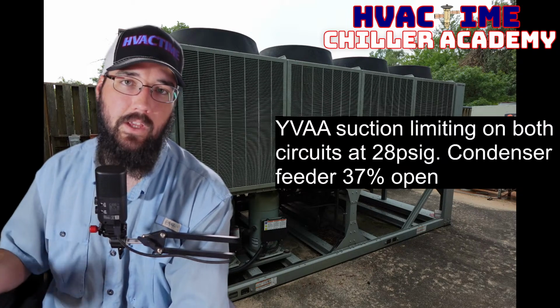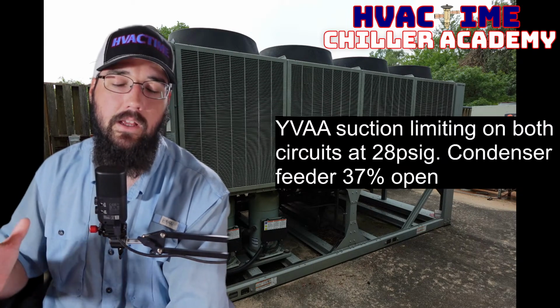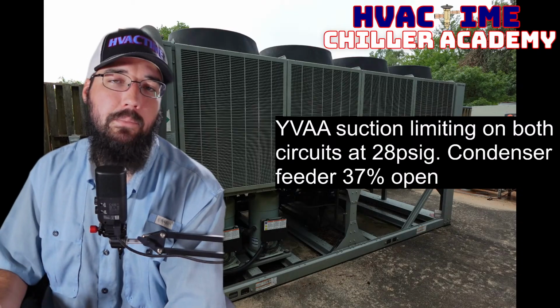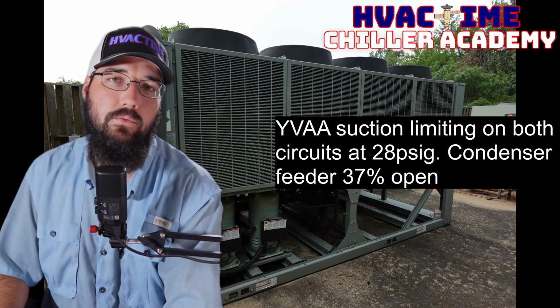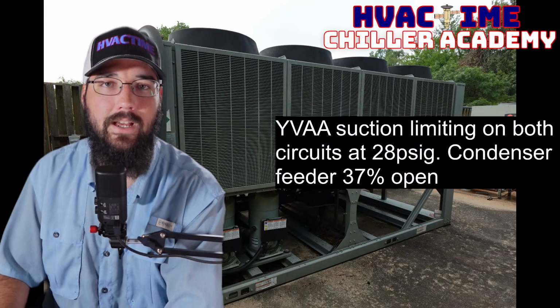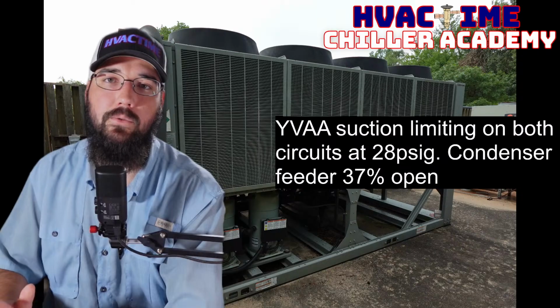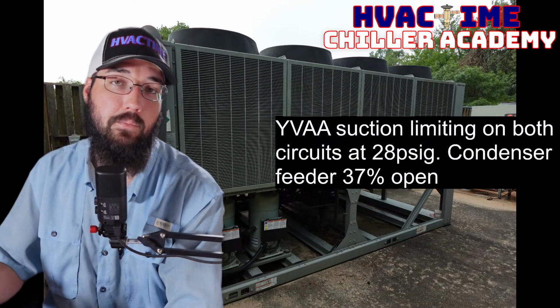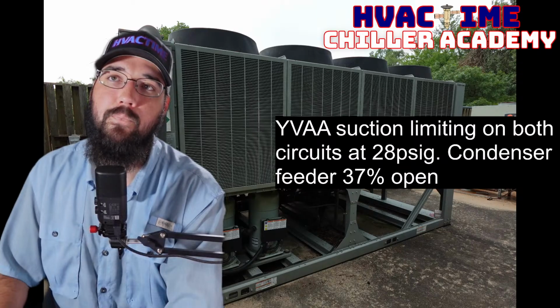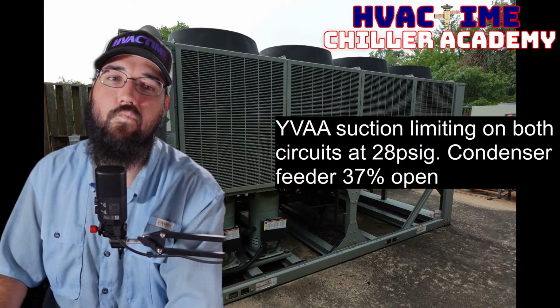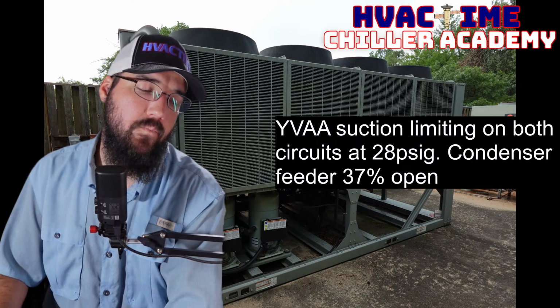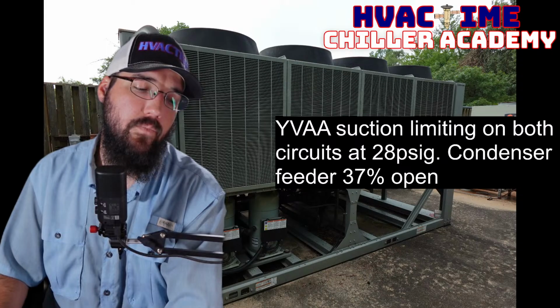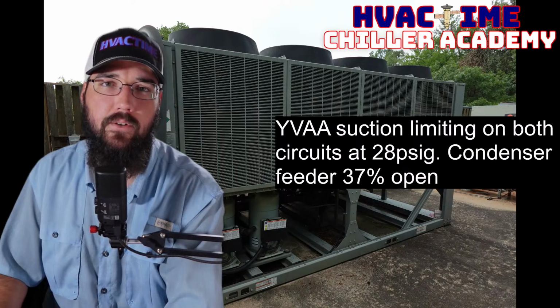Now you might say, okay, well, flow hasn't changed. We're running the same flow that we've had for forever. That may be true, that may not be. If that's an assumption, I would say don't. I would challenge the assumption. Let's actually dive in and go look and see. Did a strainer plug up? Did something happen? Do we have a problem with the pump? Yeah, I really want to verify the flow.